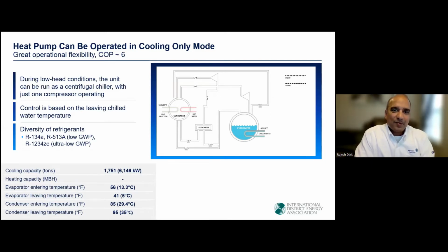So in some cases, the heat pump should be capable of running in the cooling only mode, similar to a typical water-cooled centrifugal chiller. So as you can see from the animation that Kit is playing, in this particular mode, the high stage compressor is shut off. Only the low stage compressor is operating due to the low head conditions. This practice allows the chiller to run more efficiently and take advantage of the condenser water temperatures that are well below the design. In this particular mode, the control is based on the leaving chill water, and this mode is also sometimes referred to as the heat recovery chiller mode, in which case the condenser water can be used for some domestic heating purposes.